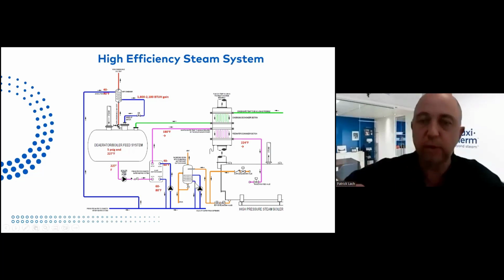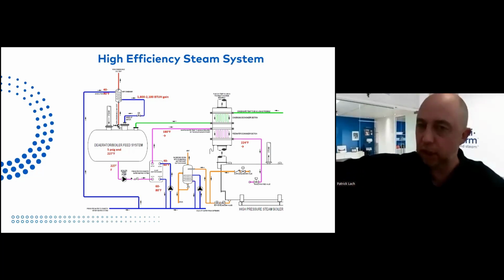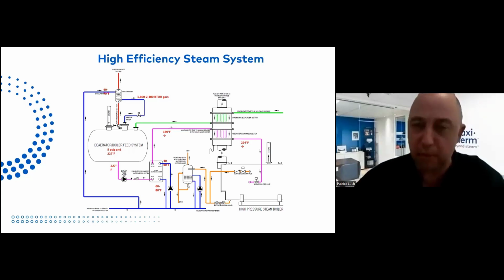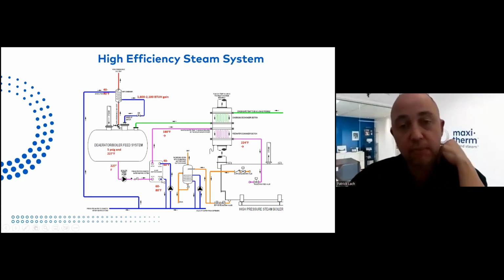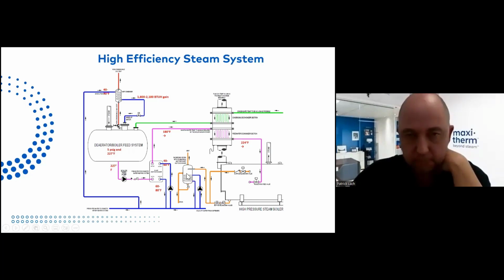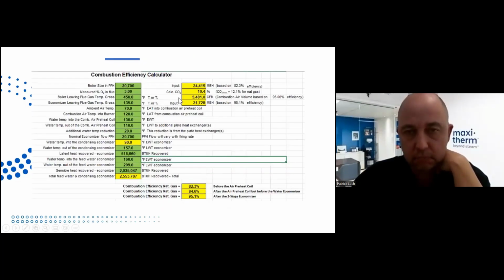If it's 100% closed loop and you use a clean steam, steam to steam heat exchanger for humidification and sterilization, then there's no makeup water. Absolutely not, right? So these pieces of equipment, like I said, might not be needed. So if you put all those numbers together, and you have this on your slide deck, that's the number you can reach. Let's say 90%, 92%. It's a huge number.